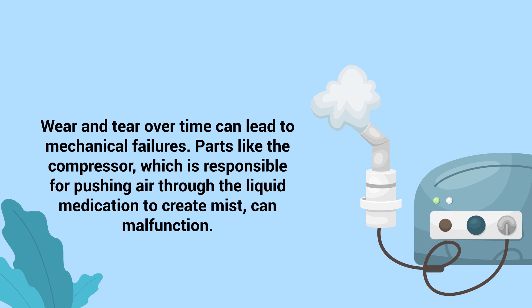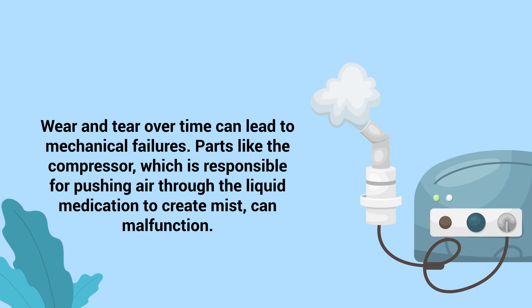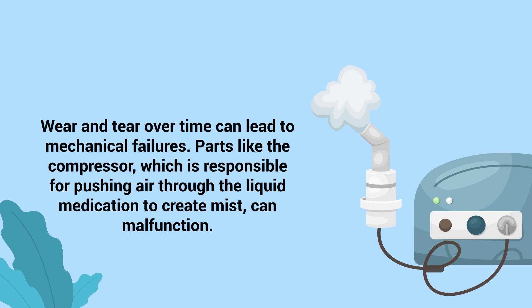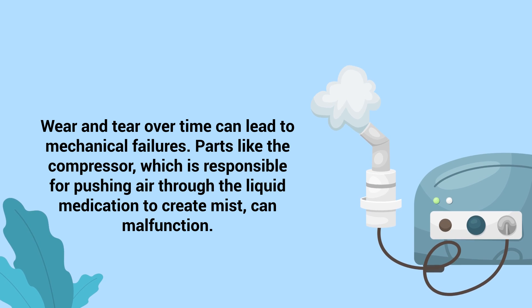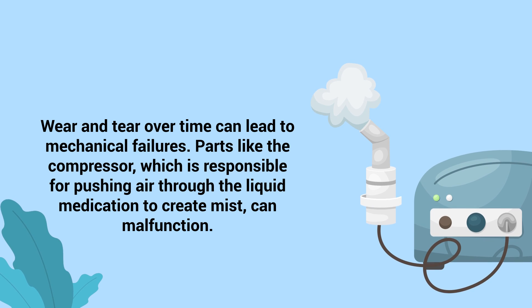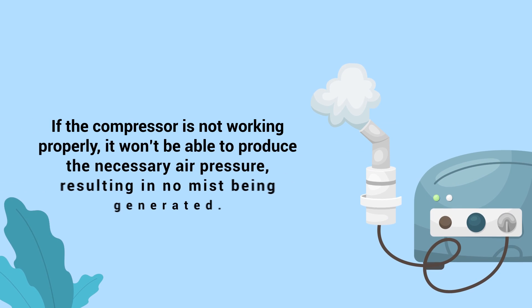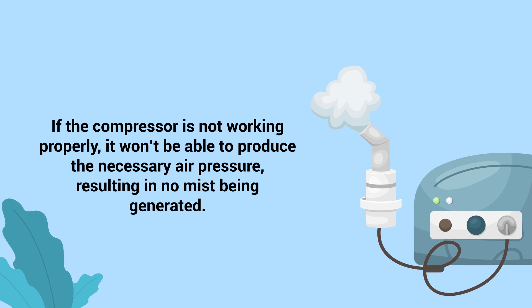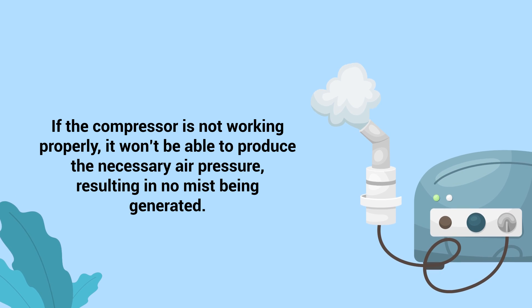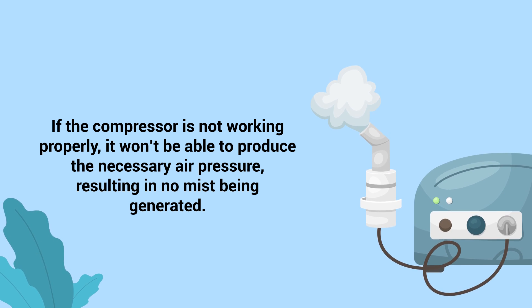Wear and tear over time can lead to mechanical failures. Parts like the compressor, which is responsible for pushing air through the liquid medication to create mist, can malfunction. If the compressor is not working properly, it won't be able to produce the necessary air pressure, resulting in no mist being generated.